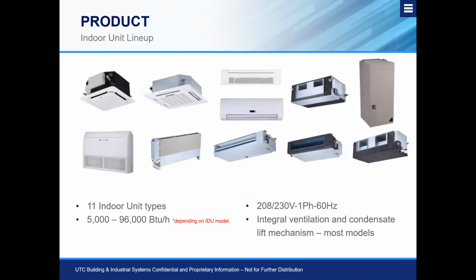And then, of course, integral ventilation on the ducted style units can be mixed in at the return. And the cassette style units do have knockouts where we can put round duct and duct outside air directly into the fan coil. Of course, the rule of thumb is that we always want to make sure that we pre-treat that outside air, as those coils, both the ducted style and the compact cassette and 3x3 cassette, cannot handle raw outside air.